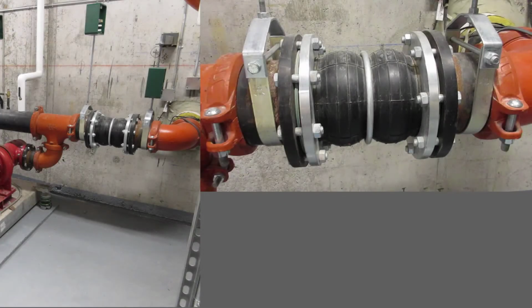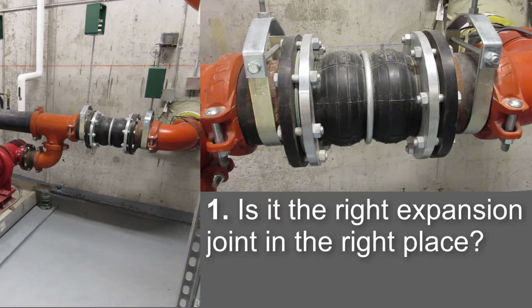So now we're ready to go through the checklist and see how good this installation of a twin sphere expansion joint is. First, is the right expansion joint in the right place? The material is neoprene, which is appropriate for indoor applications. The pressure will be fairly low since this is just before the inlet to the pumps and there isn't a large column of water on the other side of the wall, so it's definitely below the 134 psi safe working pressure limit. And the temperature will certainly be below 230 degrees Fahrenheit since this is just water returning from a cooling tower. So this one is okay.